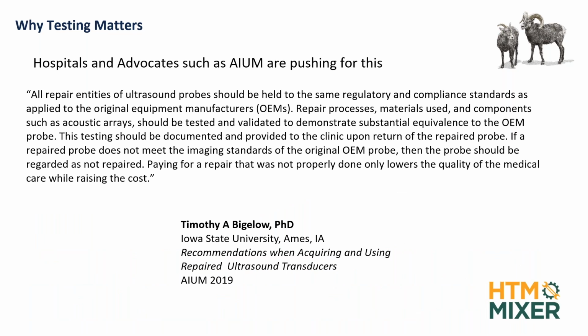Hospitals and advocates such as the American Institute of Ultrasound in Medicine are pushing for this really hard. It said any testing that should be done by the third party should be documented and provided to the clinic upon return of the repaired probe. If it does not meet the imaging standards of the OEM, then the probe should be regarded as not repaired. That one's pretty straightforward. So if the sonographer comes back and says, this stinks, what happened? That's a flag for you for a little bit of investigation.